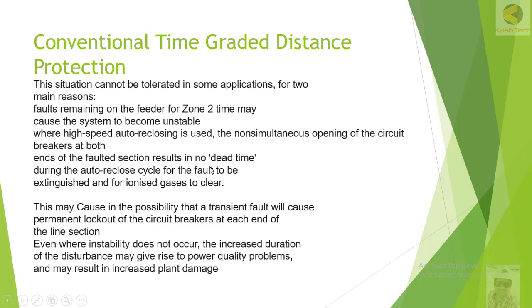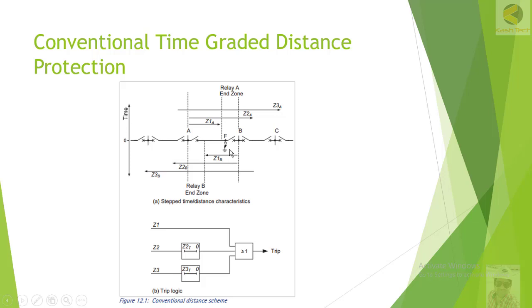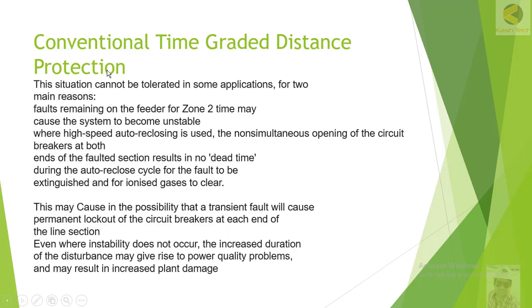Conventional time graded distance protection — this situation cannot be tolerated in some applications for two main reasons. The condition being discussed is: if there is a fault near Station B, Station B will trip immediately while Station A trips with a time delay of 250 to 400 milliseconds.